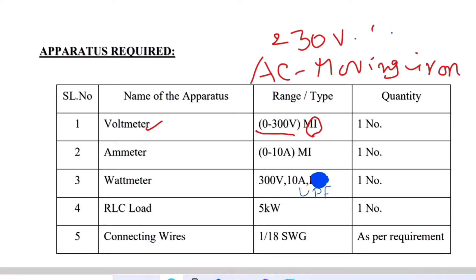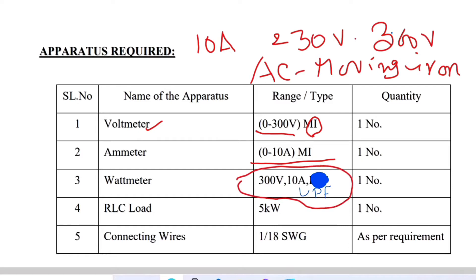The maximum range of the voltmeter reading available is only 300 V, that is why we have chosen a 0 to 300 V MI meter. The current maximum is also 10 amperes, so the ammeter is chosen in the range 0 to 10 ampere. For AC current measurement, a moving iron meter is chosen. The voltage rating of the wattmeter is 300 volt, current rating 10 amps, and the power factor is unity because the load connected is a resistive R-load.